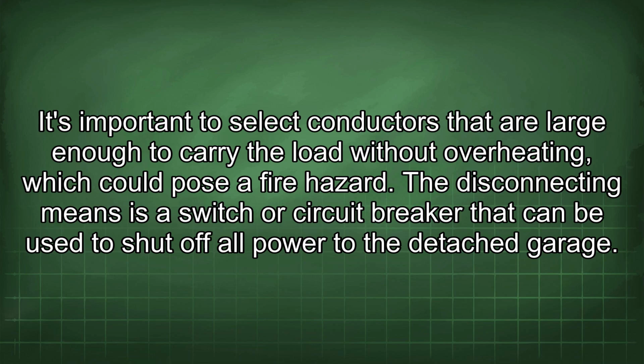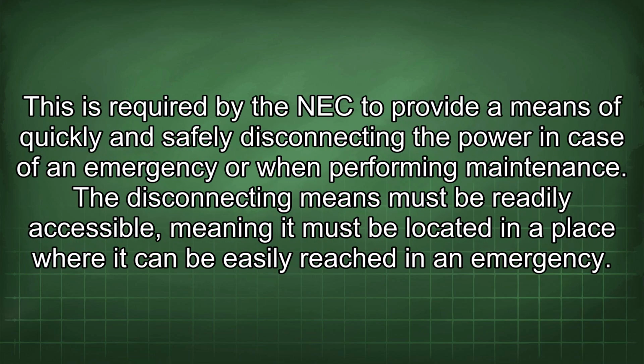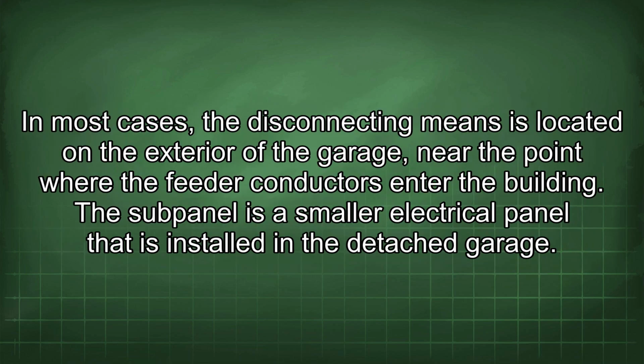The disconnecting means is a switch or circuit breaker that can be used to shut off all power to the detached garage. This is required by the NEC to provide a means of quickly and safely disconnecting the power in case of an emergency or when performing maintenance. The disconnecting means must be readily accessible, meaning it must be located in a place where it can be easily reached in an emergency. In most cases, the disconnecting means is located on the exterior of the garage, near the point where the feeder conductors enter the building.